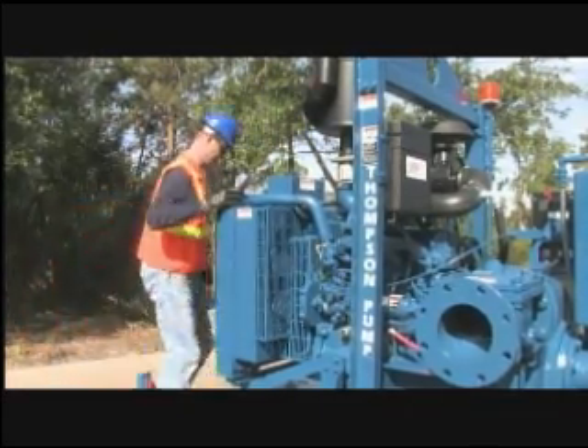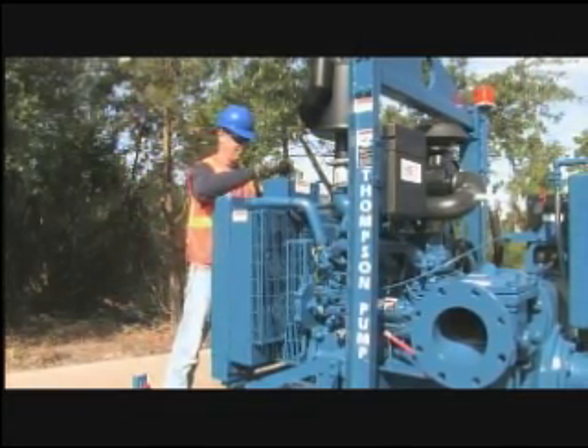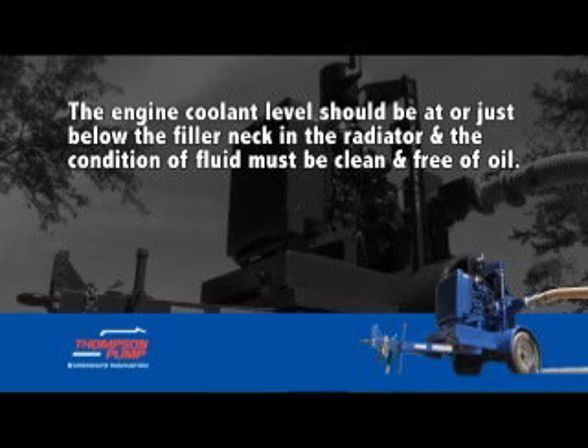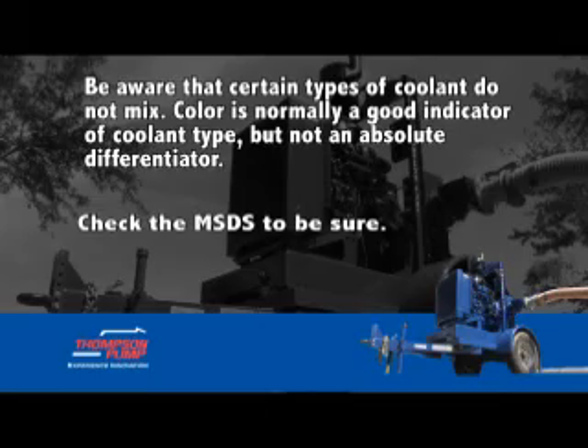If your Thompson Pump is equipped with a water-cooled engine, it is important that you check the engine radiator coolant level and condition when the engine is not hot. The engine coolant level should be at or just below the filler neck in the radiator, and the condition of the fluid must be clean and free of oil. Be aware that certain types of coolant do not mix. Color is normally a good indicator of the coolant type, but not an absolute differentiator. Check the MSDS to be sure.